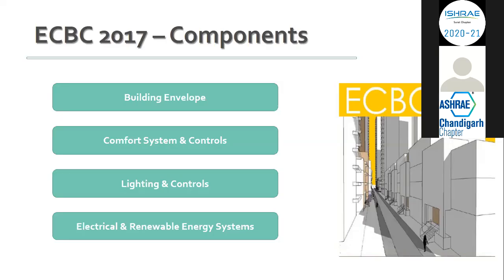You need to implement measures like replacing HVAC systems with 5-star rated systems, replacing fans with super-efficient fans, and replacing single-glazed glass with double-glazed glass. You can provide heat-reflective tiles at the rooftop, and add insulation over the wall or roof to reduce heat ingress. You can install capacitor banks to increase your power factor—if it's around 0.8 or 0.85, you can increase it to more than 0.97 or 0.99. You can replace electrical appliances and lighting systems, and integrate with BMS systems. In that way, your existing building would definitely convert to an energy efficient building.